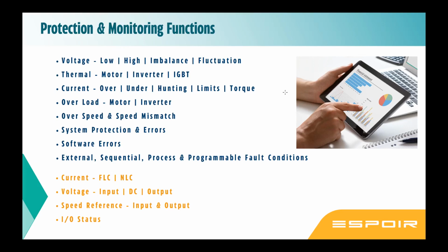MFMs to achieve this. You can monitor the current. Could be a full load current, no load current, voltage, input, DC, output. All three you can check. Speed reference you can check. Input frequency, output frequency, input speed, output speed. These are all theoretical values. You can calibrate to a certain point. This cannot be a very accurate view, but just for continuous monitoring, these aspects are good.